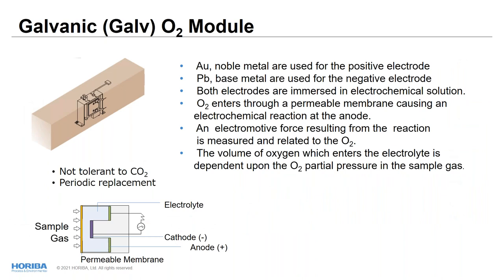And lastly, the galvanic O2 module. This is one of the smallest O2 sensors. It uses this type of detection. There is an anode right here and a cathode here. Both electrodes are immersed in an electrochemical solution. Once oxygen enters through the permeable membrane, it causes an electrochemical reaction at the anode, right? An electromotive force resulting from the reaction is measured, and it is related to the oxygen concentration. That's how the galvanic O2 module works.